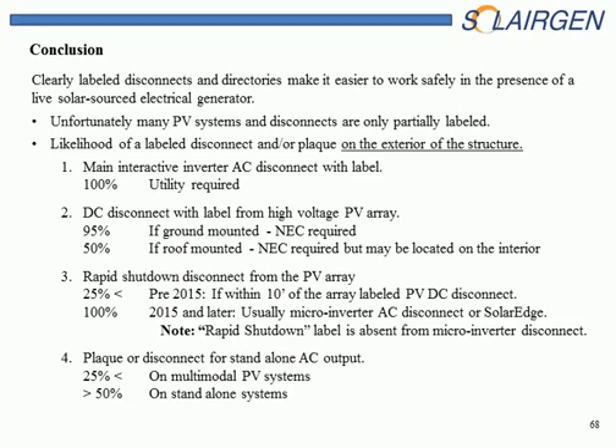The DC disconnect. Now, if it's a low voltage microinverter system or a PV optimized SolarEdge, then you're in the 100% zone. But if it's a high voltage PV array that doesn't have the voltage safe optimizer, if it's a ground mounted system, probably 95% of the time that DC disconnect will be accessible on the exterior. It may be higher than that. But if it's roof mounted and it's one of the older inverters that has the high voltage, then probably 50% of the time. The other 50% is going to be inside somewhere.